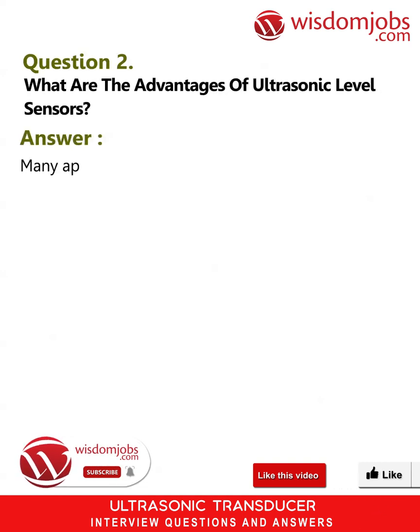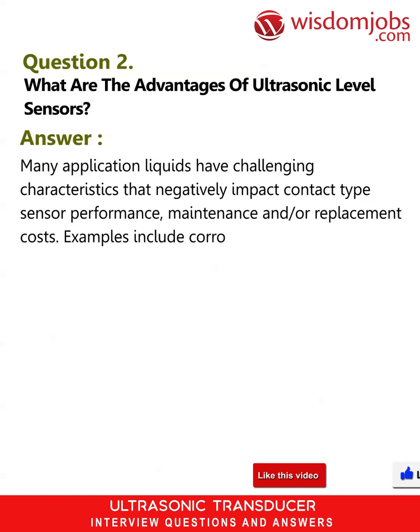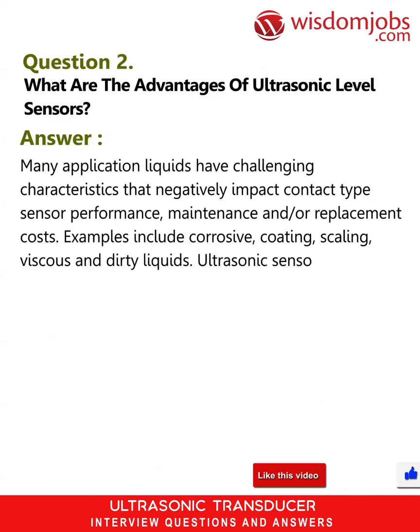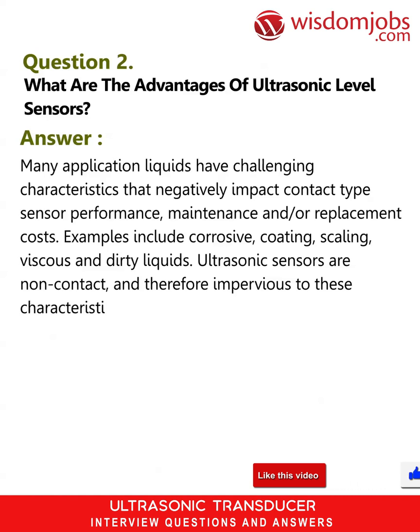Question 2. What are the advantages of ultrasonic level sensors? Answer. Many application liquids have challenging characteristics that negatively impact contact type sensor performance, maintenance and/or replacement costs. Examples include corrosive, coating, scaling, viscous and dirty liquids. Ultrasonic sensors are non-contact, and therefore impervious to these characteristics.